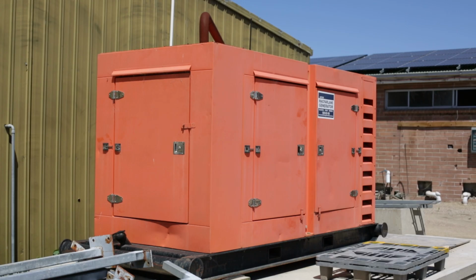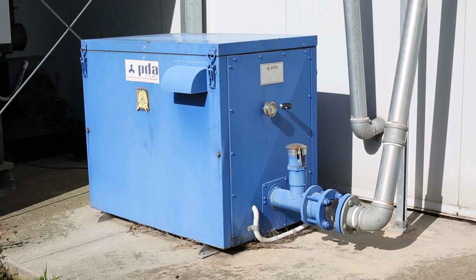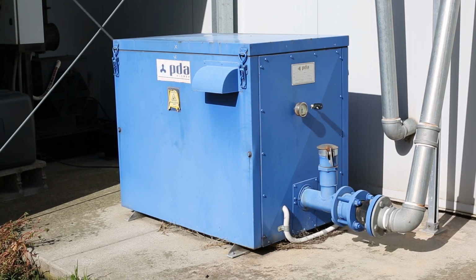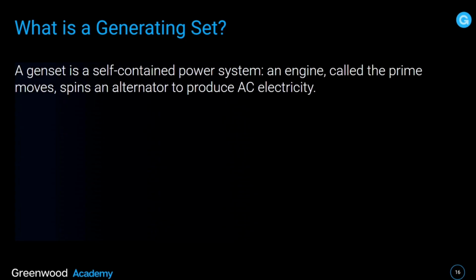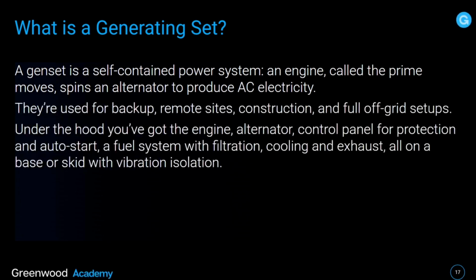Now, a GENSET is a self-contained power system, an engine called the prime mover, and it spins an alternator to produce AC electricity. And they're used in a variety of situations as backup, remote sites, construction and full off-grid setups. Now, under the hood, you've got the engine, alternator, control panel for the protection and auto start, a fuel system with filtration, cooling and exhaust, all on a base or a skid with vibration isolation.